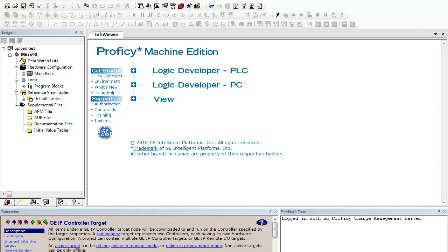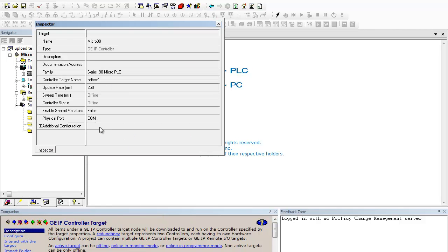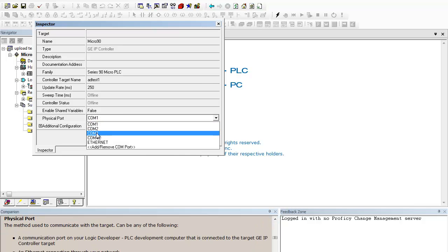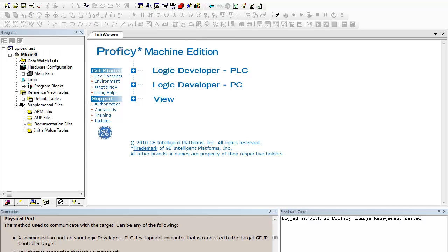Let's go online with it. It is kind of opposite of what you might expect — if there is not a red X, that means you are not communicating to it, or you are not online. So you can go online here, but first let's set up the properties. The default is COM 1, and we know our cable is COM 3. That is really the only thing we have to set up; everything else we will leave as default.